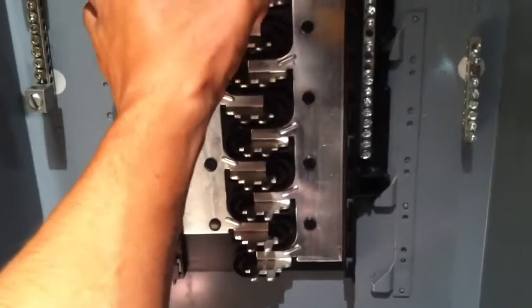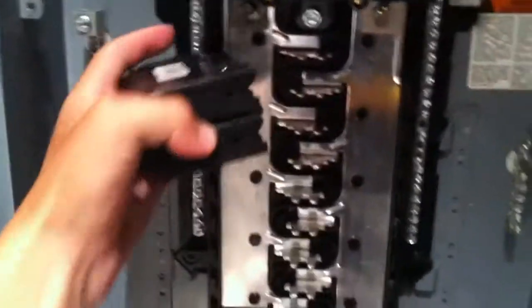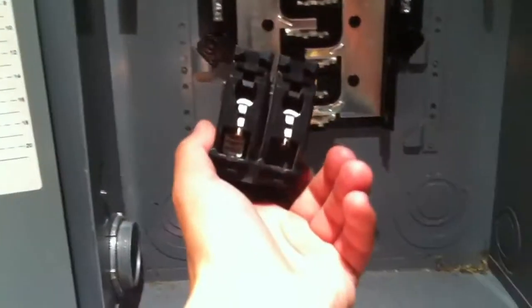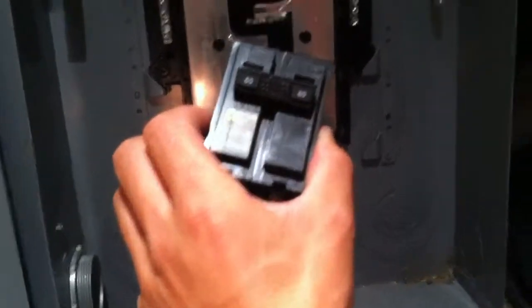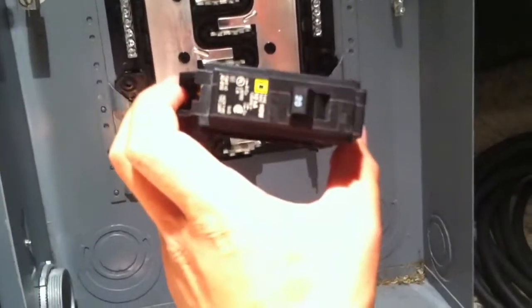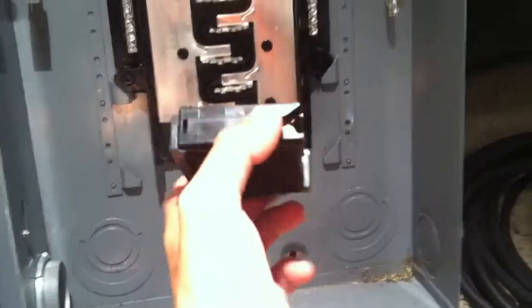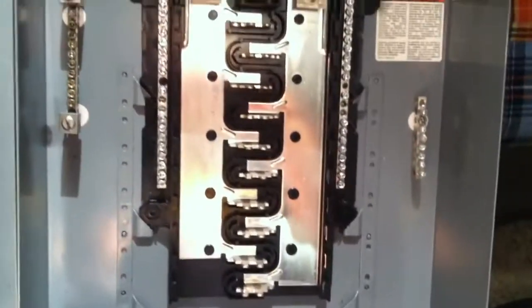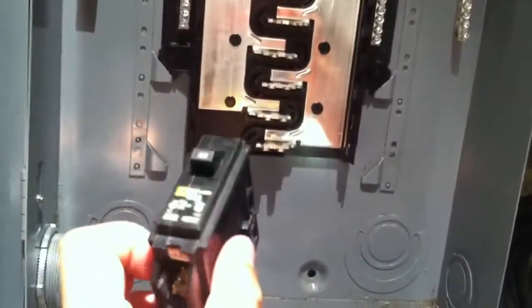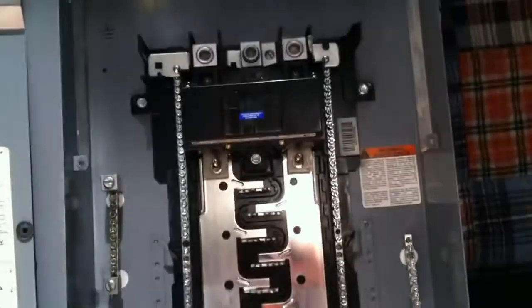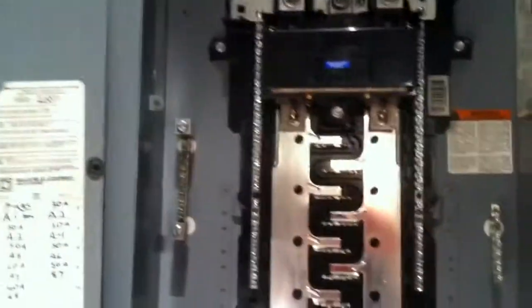Now, this isn't a full-blown tutorial. You're going to have to know stuff like wire gauges. 60 amp breaker, you need number 6 wiring. 20 amp breaker, number 12 wiring. Don't go into your breaker box and say, that 15 amp breaker trips all the time, so I'm going to pop a 20 in there. There's reasons why there's 15 amp and 20 amp breakers. You have to know the wire gauges and all that stuff. Yes, I know all that stuff, but this is not a tutorial on it, and it would go forever if I showed you how to wire all that up.